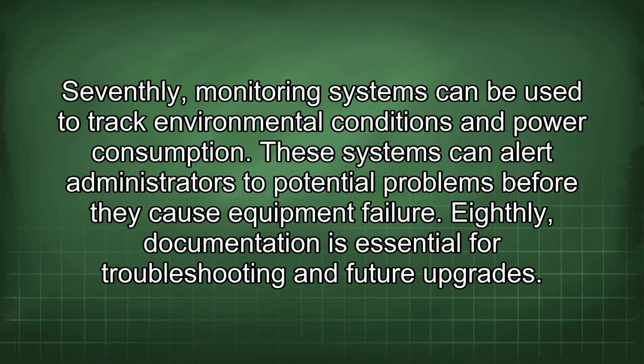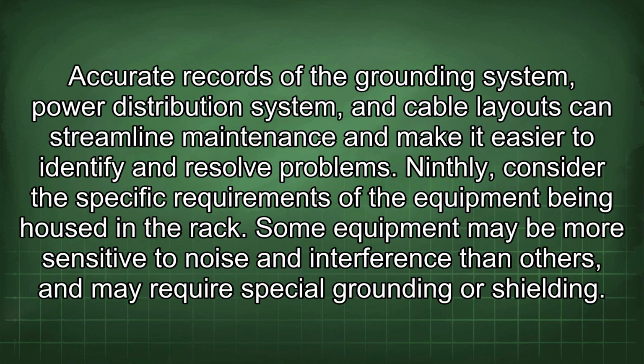Seventhly, monitoring systems can be used to track environmental conditions and power consumption. These systems can alert administrators to potential problems before they cause equipment failure. Eighthly, documentation is essential for troubleshooting and future upgrades. Accurate records of the grounding system, power distribution system, and cable layouts can streamline maintenance and make it easier to identify and resolve problems. Ninthly, consider the specific requirements of the equipment being housed in the rack.